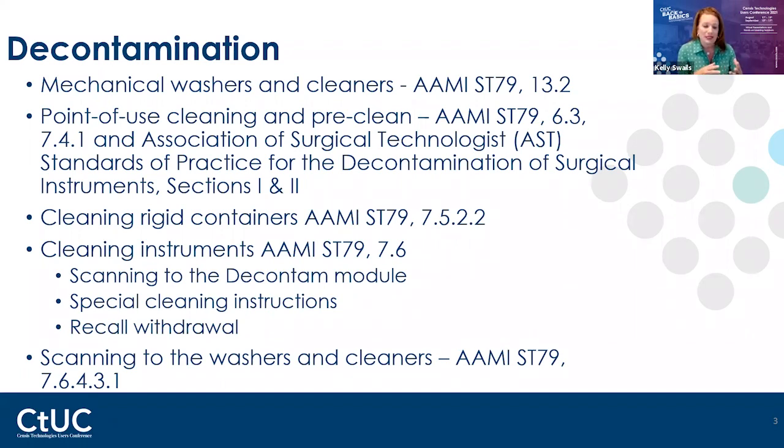But one thing that I'm seeing a lot is that people are not performing a wash test in their cart washer. Well, a cart washer is a mechanical washer, so we need to test that according to AAMI guidelines. And I'm guessing it's probably in your IFU too, or the manual for your washer, that says it. So many times I hear, yes, but we don't process instruments in our cart washer.